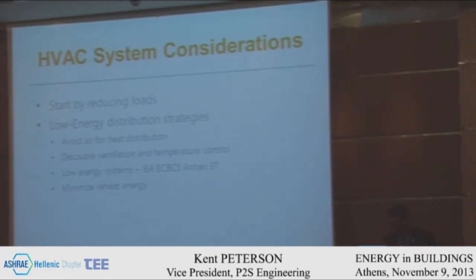HVAC system considerations: we want to reduce loads significantly. A big energy consumer in commercial buildings is heating air that's already been cooled down. A standard example might be a variable air volume system with reheat, where we're doing a lot of reheat, and we're trying to reduce the amount of reheat in many of the buildings that are out there.